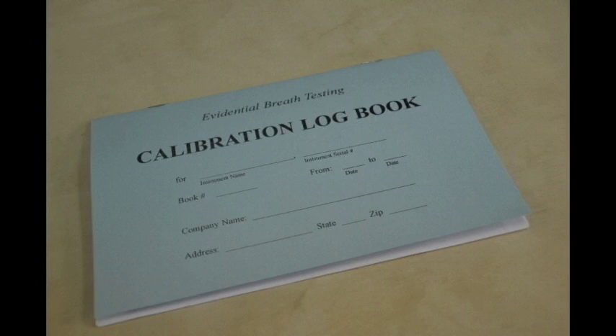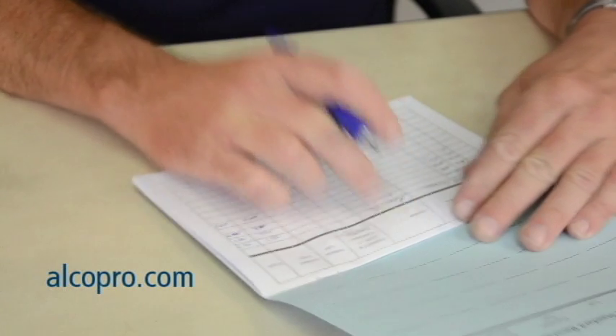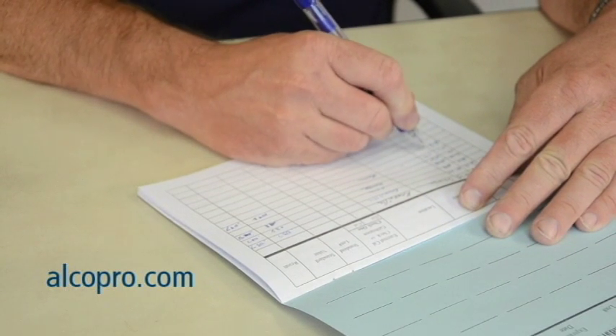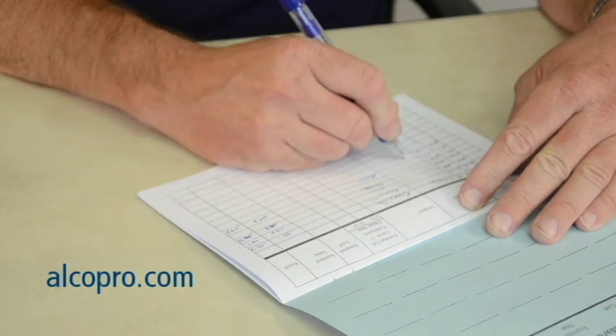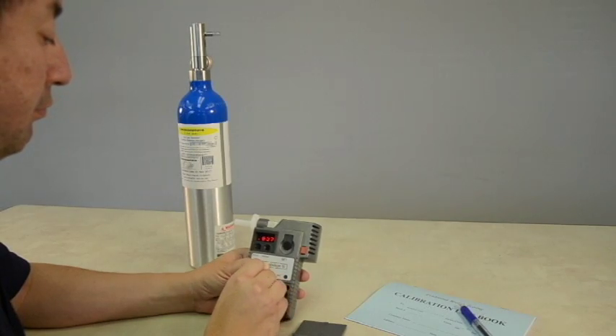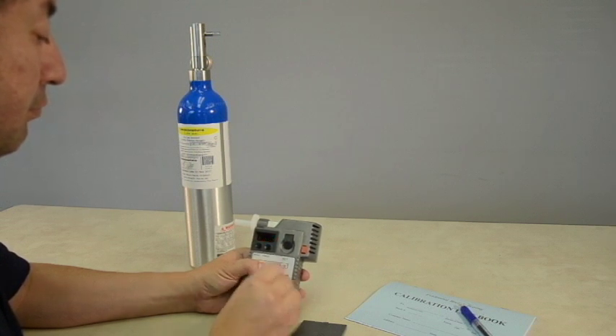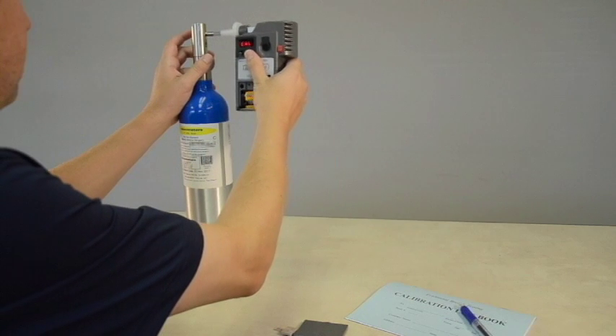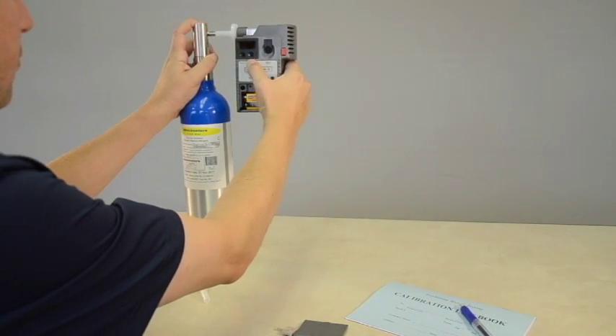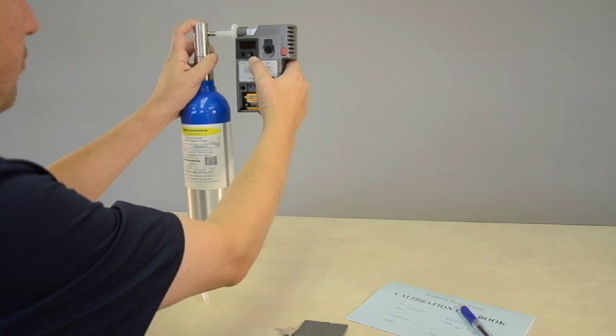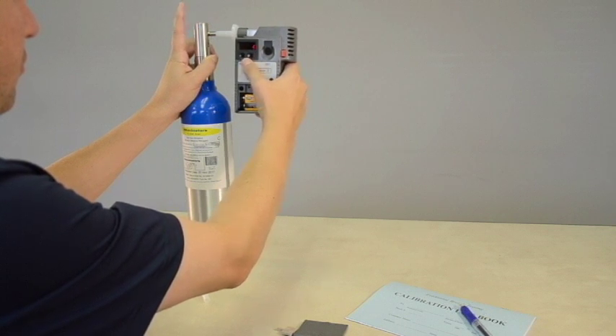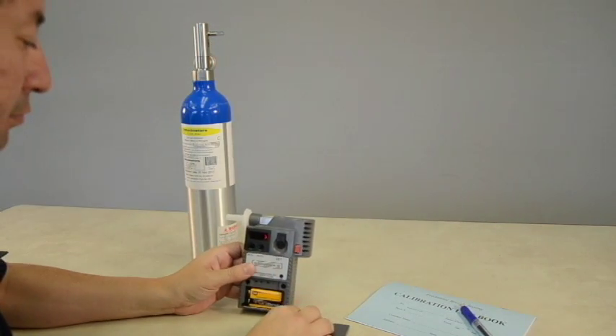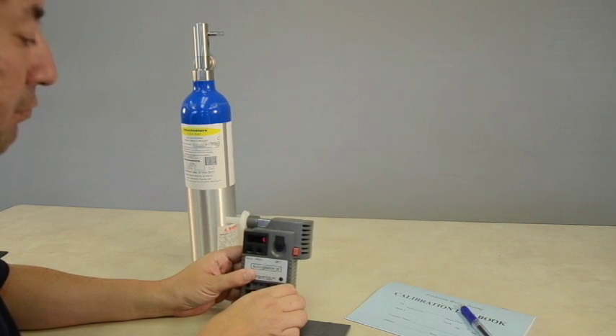It is a good idea to keep a logbook of accuracy checks and calibrations performed on your device. You can purchase an accuracy check calibration logbook at alcopro.com. A calibration or calibration adjustment is a procedure for setting the device or instrument to a known standard. A best practice is to allow only certain staff who are proficient in the calibration procedure to perform a calibration adjustment. Before performing a calibration, you must first locate the expected value of your gas standard.